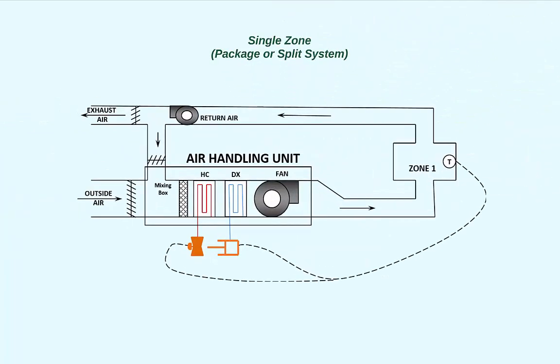Now that we have discussed, in excruciating detail, how the refrigeration cycle is controlled internally, let's look at some typical direct expansion cooling applications you likely have on your installation. The simplest system is a single zone package unit or split system. This design is typical in residential homes and department stores. Cooling is provided by the refrigeration cycle DX unit, which is controlled based upon the zone temperature using two-position control. When the zone temperature rises above set point, the controller sends an on signal to the DX unit's control panel. From there, the unit could close a relay to energize the compressor and start the refrigeration cycle.